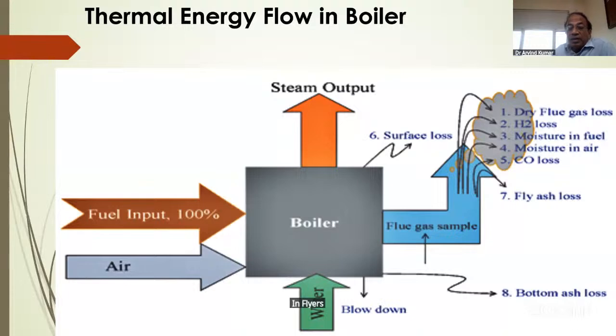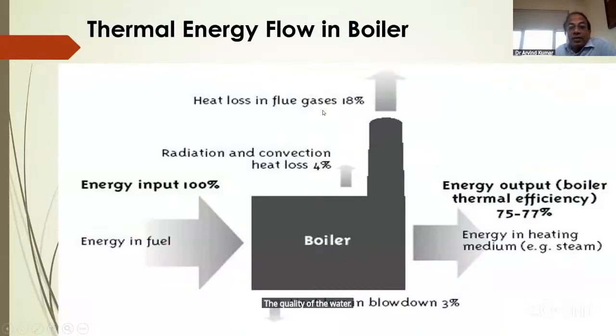And there are fly ash losses and bottom ash losses. The ash comes in two forms: the clinker form is the bottom ash, and the fly ash is the suspended particulate matter that goes with the exhaust gases. It also contains heat, and it is problematic for the environment. Then there are the residual blowdown losses: the sediments are deposited continuously at the bottom, and we have to force a blowdown periodically. So water treatment in that regard is very important, the quality of the water. That is the pattern of different types of losses that occur in a boiler.